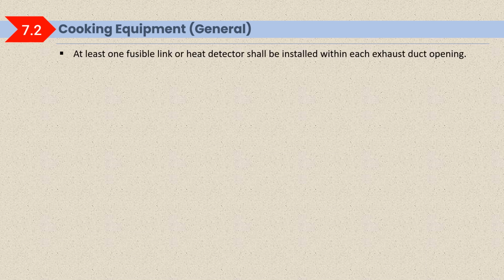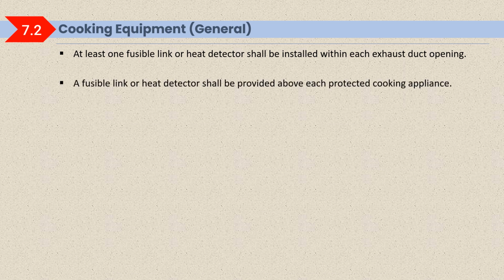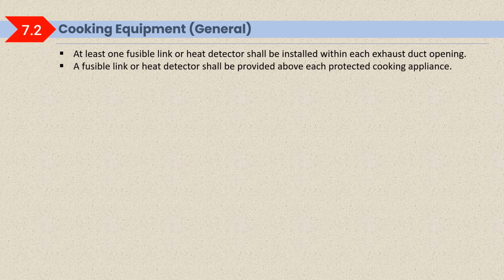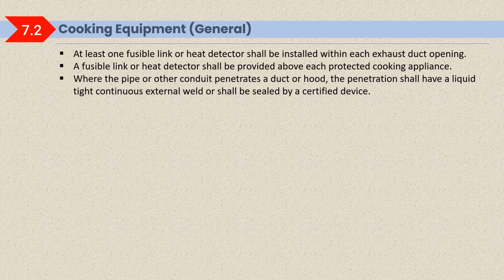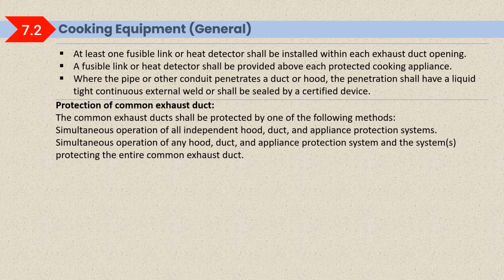At least one fusible link or heat detector shall be installed within the exhaust duct opening. A fusible link or heat detector shall be provided above each protected cooking appliance. Where the pipe or other conduit penetrates a duct or hood, the penetration shall have a liquid tight continuous external weld or shall be sealed with a certified device. Protection of common exhaust duct.